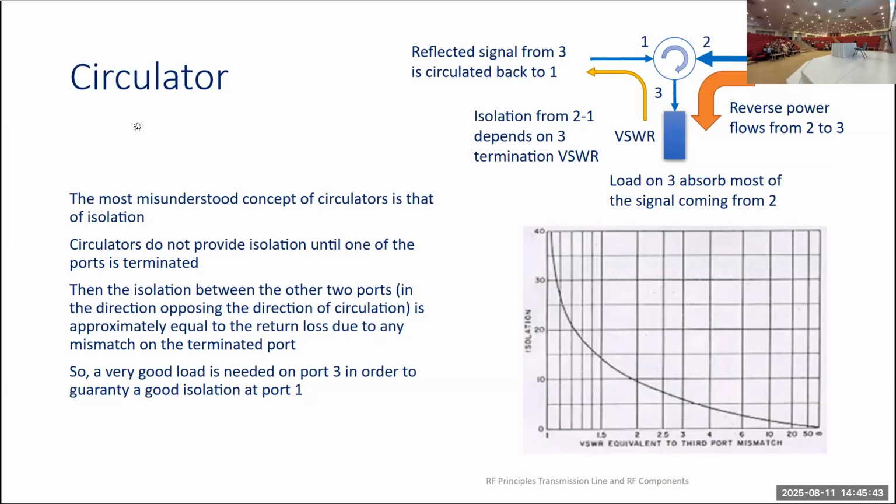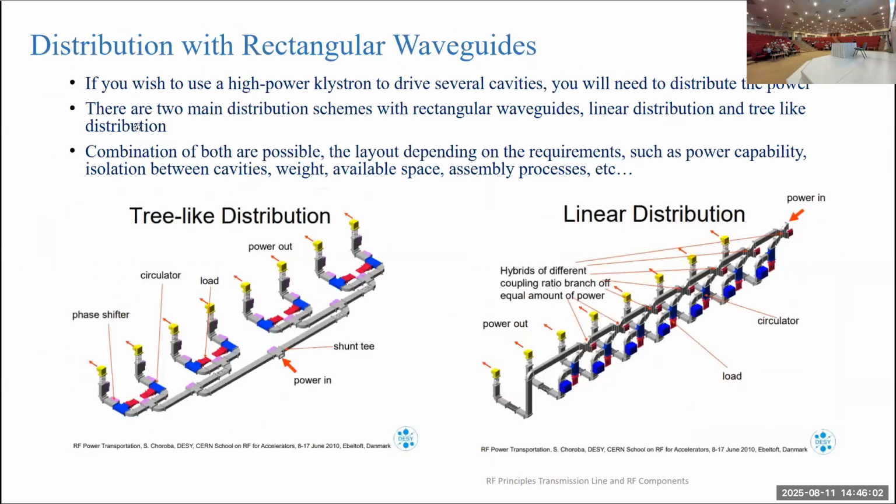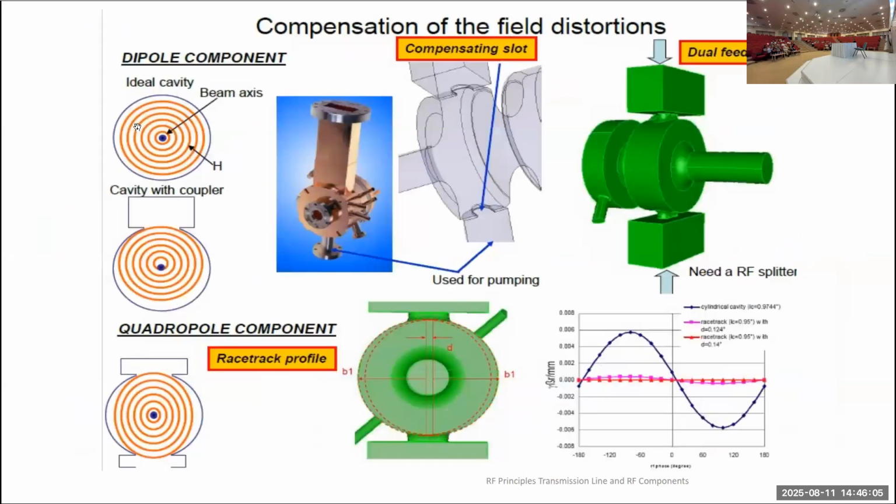So when you have two rectangular waveguides coupled to a circular cavity, you showed the TM mode is distorted, right? If you have one arm instead of two arms, let me show where I have shown this. This one. For two arms, can you feed from one arm and use the other arm with the plunger? No, here we are not using a plunger. Here we are using only RF to the accelerating structure.